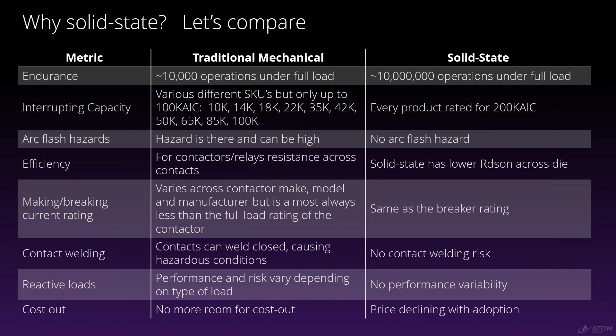So what that does is it limits the amount of energy that is through the breaker. So you pretty much eliminate any arc flash hazard. The incident energy after our breaker is so low that class 0 PPE is really required. It's amazing stuff. The efficiency, we have a lower RDS on across the die than using a contactor and a relay with the resistance across the contacts. The making and breaking rating are the same, but you don't have to worry about contact welding any longer because there are, again, no moving parts. And you don't have to worry about any kind of performance variability. And the best part is, as this technology is adopted, the price will continue to decline, where a traditional circuit breaker has been around for over 100 years. They have completely optimized the cost of that device.